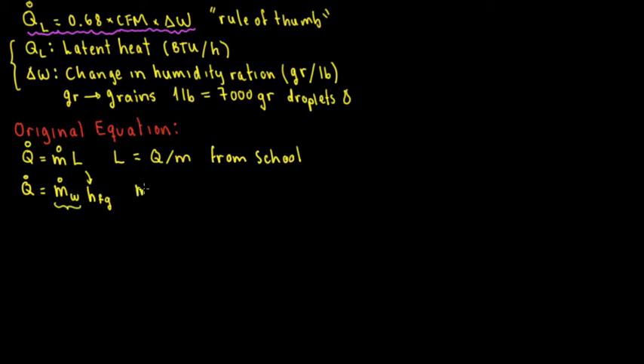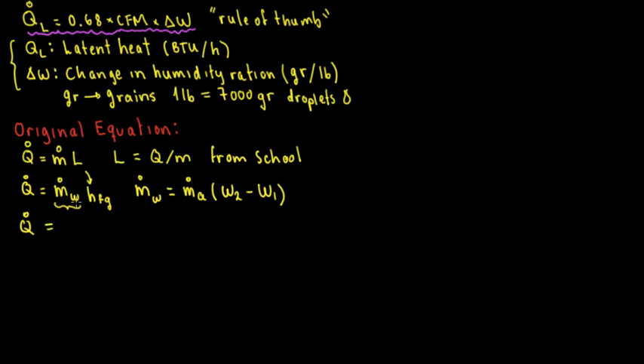The mass of water vapor is going to be equal to — as we've seen in other videos — mass of dry air times the difference of humidity ratio, delta W. So Q-dot of latent heat is going to be equal to mass of air times delta W times specific enthalpy h_fg, which is the latent heat.